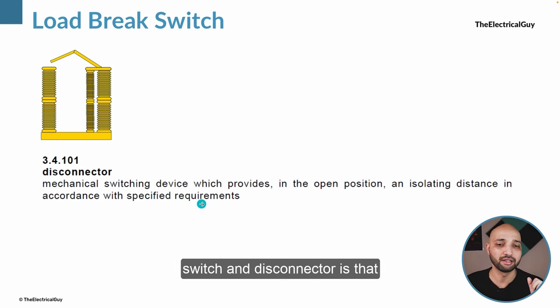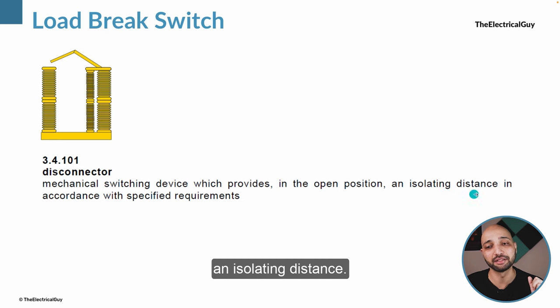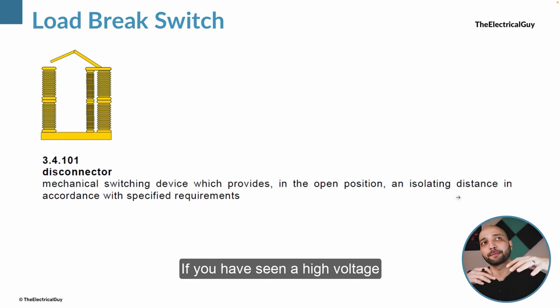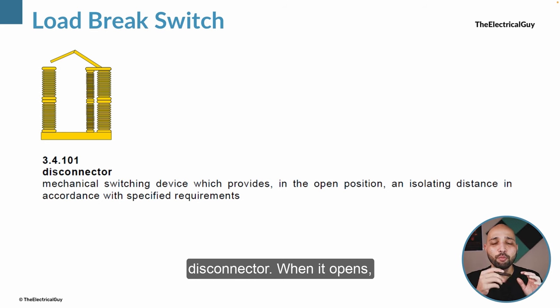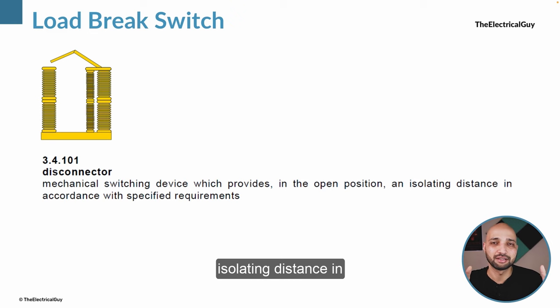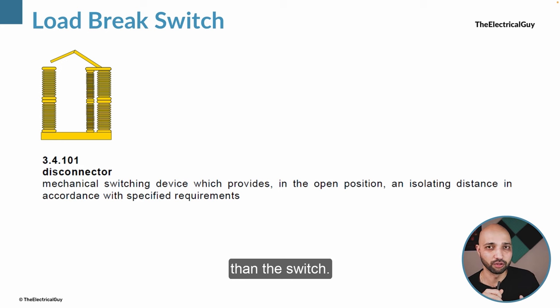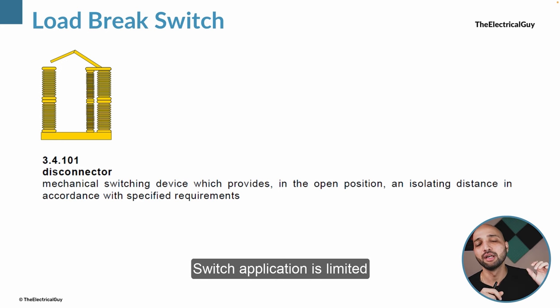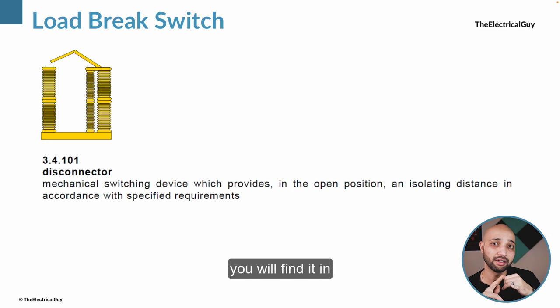The difference between switch and disconnector is that the disconnector also provides an isolating distance. If you have seen a high voltage disconnector, when it opens you will see it maintains a very large distance between the two live contacts, providing a significant isolating distance in the switchyard. Switch application is limited to low voltage and medium voltage, but disconnectors you will find at medium voltage, high voltage, and extra high voltage as well.